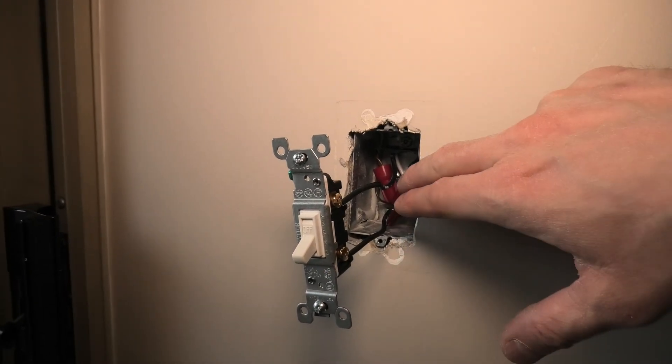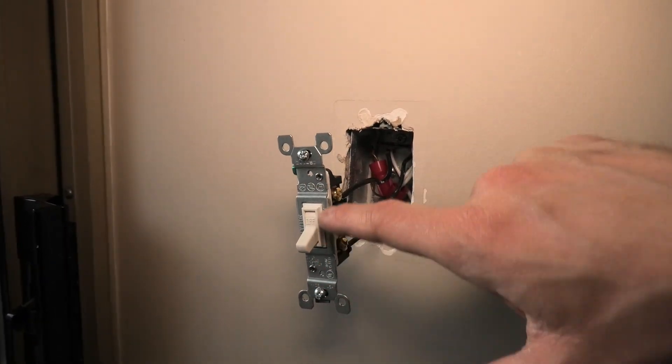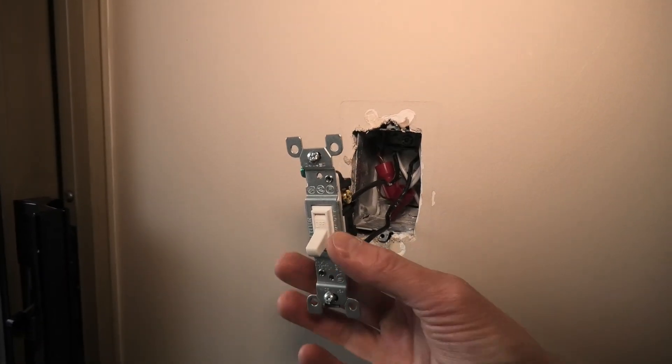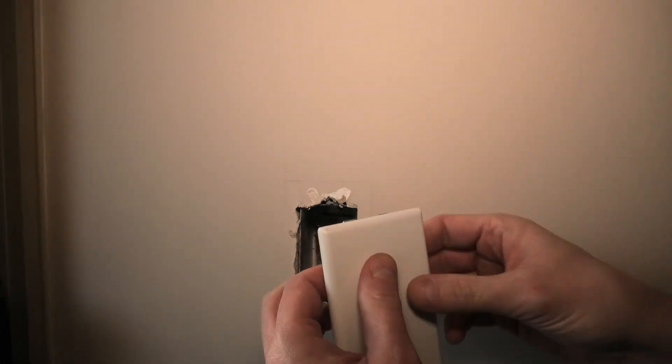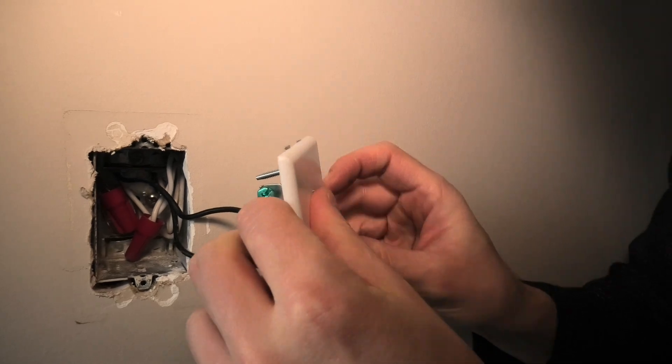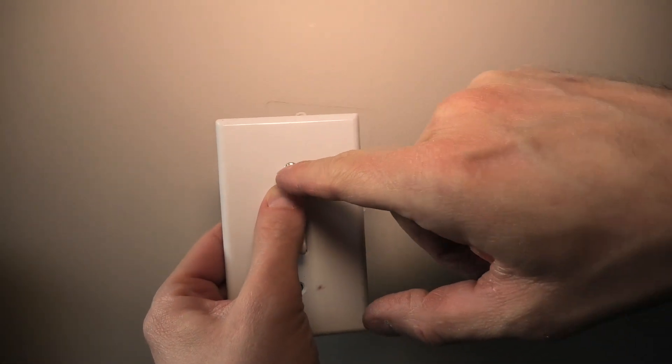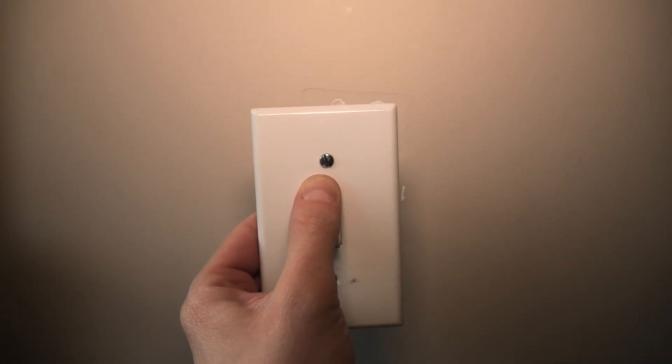And again, the box is not grounded and the switch is not grounded. In this case, this bracket would become energized. And besides that, once we have our plate installed, guess what would happen? This screw would be energized as well.